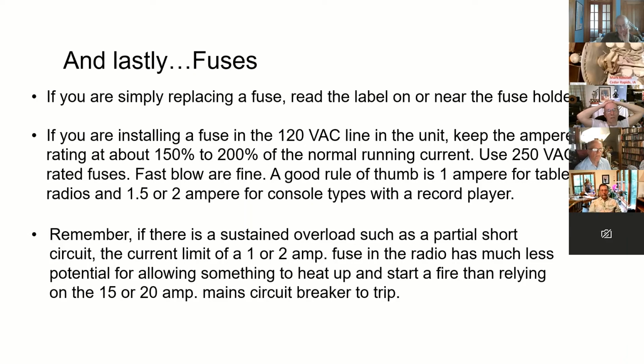But a fuse like this is going to blow more reliably and faster, and with less arc damage or chances of sparks flying and starting the cabinet on fire, than relying on that 15 or 20 amp circuit breaker on the mains to trip. And that's what I got.